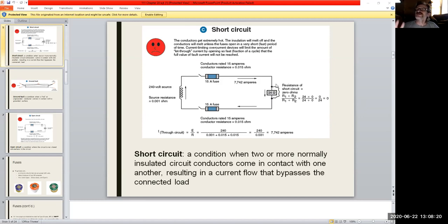And a weird situation, and let's say, being nylon, if they get hot for a given amount of time, the insulation can melt off. And when it does, you end up getting wires crossed. I don't want to say it's a common occurrence, but this does happen, and there are different reasons why. We could go back and analyze what happened. Maybe the staple they were using to apply the Romex was pounded in too much and was putting too much stress on the wire. Then over time with heat and whatnot, it ended up becoming disengaged. There are so many different scenarios we could follow through to see why the insulation comes away. There are so many different causes, but the result is the same.